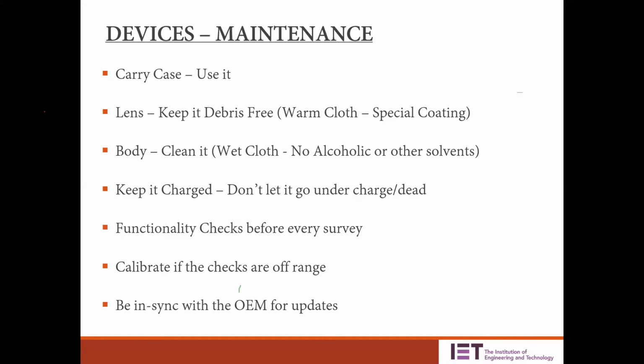So I have seen, like I said, I have seen some people removing this coating. I have seen some imagers in which they have accidentally cleaned the lens with some alcoholic solvent, thinking that it will be better after cleaning, and the alcoholic solvent has damaged the coating. It's gone. When it's gone, your imager will act like an opaque device to the incoming photons. Once the photons don't land on the sensor through the imager, your readings will be well off. So be careful with the lens, because there is a special coating. If you take your device out, you will see that your lens is really shiny from the outside. The reason is that there is a special coating to enable the photons into the image sensor.